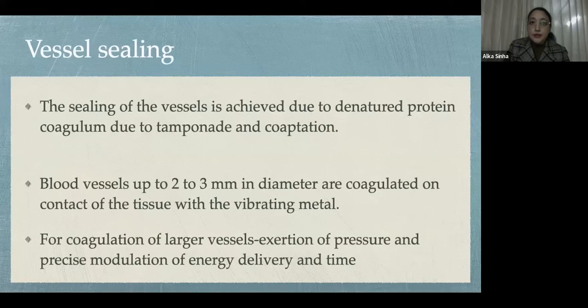What is important to us when doing surgeries like hysterectomy is the vessel sealing effect. Sealing of the vessels is achieved due to formation of a denatured protein coagulum from tamponade and coaptation of the vessel walls. Blood vessels up to 2 to 3 millimeters in diameter are coagulated just by contact of the tissue with the vibrating metal. However, for coagulation of larger vessels, exertion of pressure is required, as well as precise modulation of energy, time, and delivery, as we'll discuss in later slides.